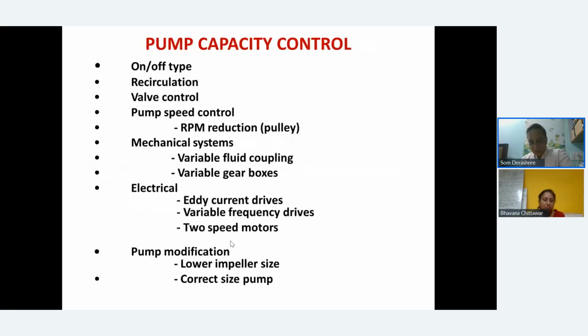Now, pump capacity control. Yes, you can have on-off, recirculation, valve control, and pump speed control through reduction pulleys. Mechanical systems include variable fluid couplings or variable gearboxes. Electrical options include eddy current drives, variable frequency drives, and 2-speed motors. Pump modification itself, you can change to a lower impeller or correct the pump size, etc. So these are all the mechanical, electrical, and pump design modifications that you can do.